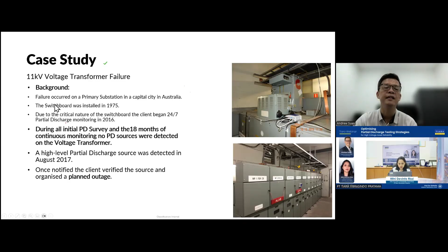Once the alert was triggered, we went down and took a look. We found from the graph that the PD source rose from 2 dB to 8 dB in a 10-minute period. On the 4th of August, there was a high rise in the sound energy, it went up very high, and then it never went down. Then the alarm was triggered. We checked, and we confirmed this is a real PD signal. We informed the owner, and 2 weeks later, they planned the outage.